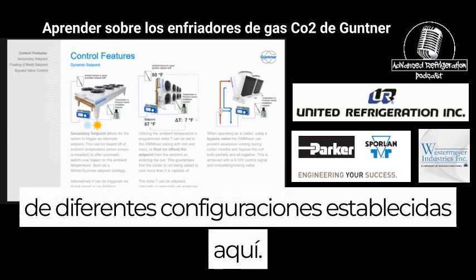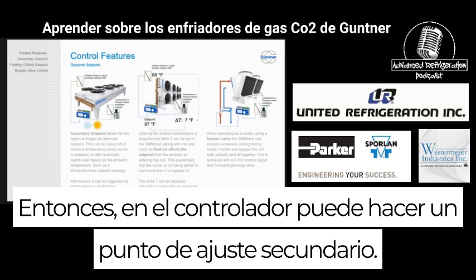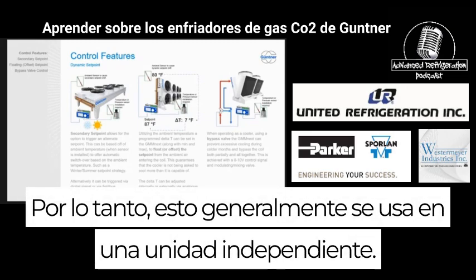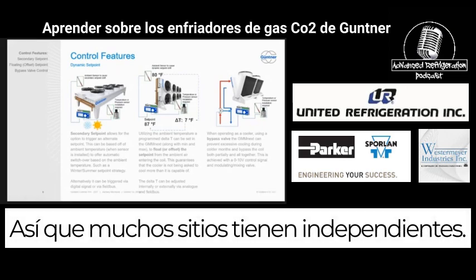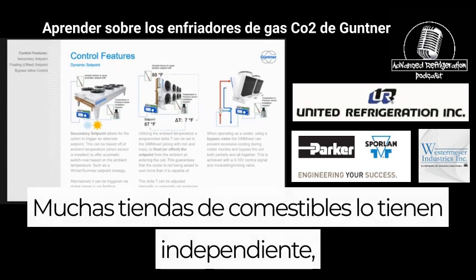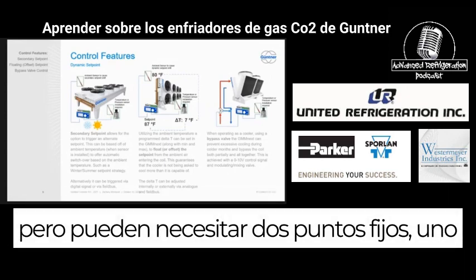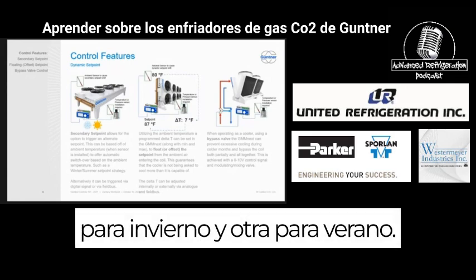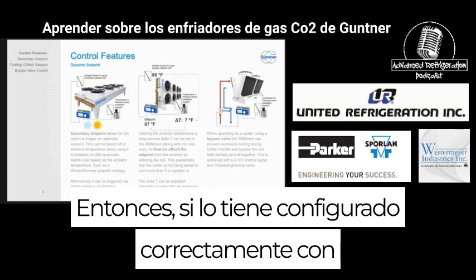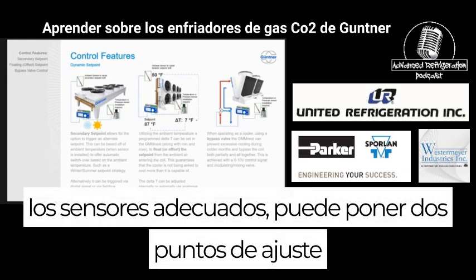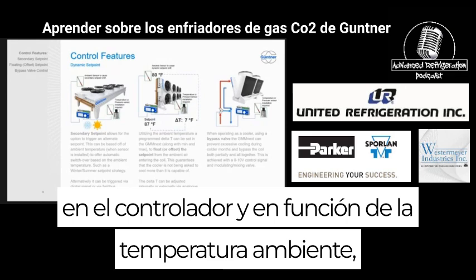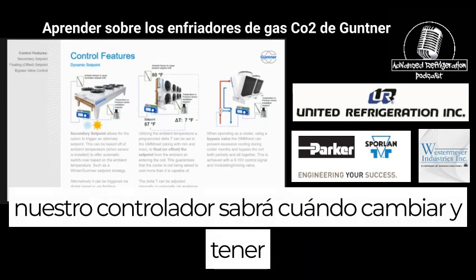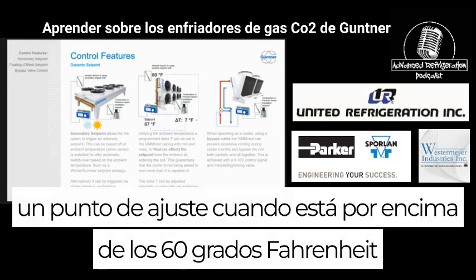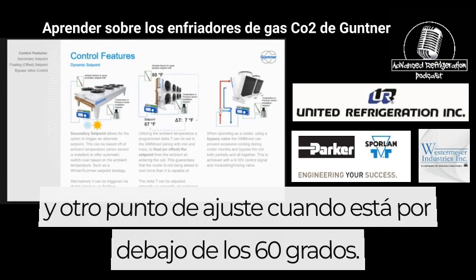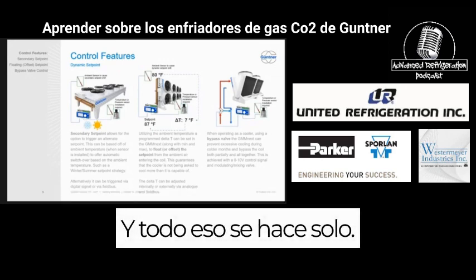There's also a lot of different settings on here. On the controller, you can do a secondary set point. This is usually used on a unit that's standalone. A lot of sites don't have a BMS system. A lot of grocery stores have it standalone, but they might need two set points, one for winter and one for summer. If you have it set up properly with the proper sensors, you can put two set points in the controller, and based on the ambient temperature, our controller will know when to switch and have one set point when it's over 60 degrees Fahrenheit and another set point when it's under 60 degrees. And that's all done by itself.